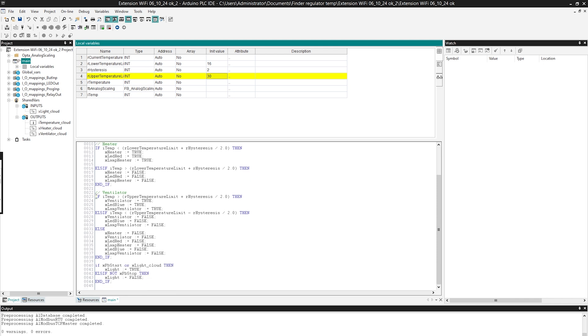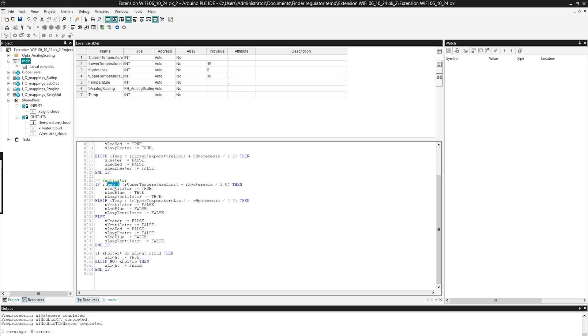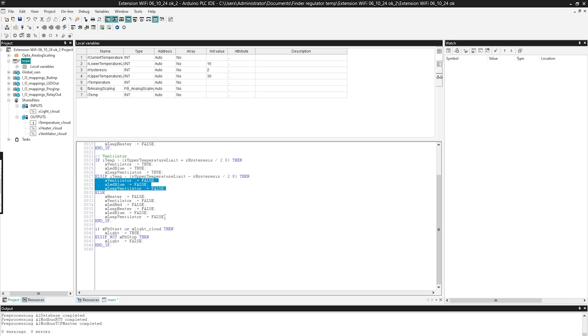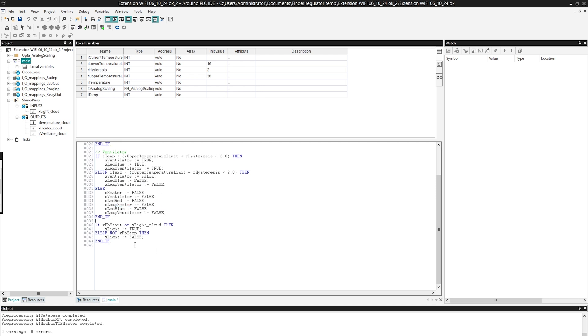Here I have an if condition: if the temperature is greater than the upper limit, which is 30 degrees Celsius plus half of the hysteresis, then turn on the ventilator and turn on the indicator light. At the bottom there is the last line of the code — we simply turn on the lighting in the control cabinet using the start button or a button in the cloud. It is a simple if condition: if this condition is met, we turn on the lamp; otherwise, if the stop button is pressed, we turn off the lamp.